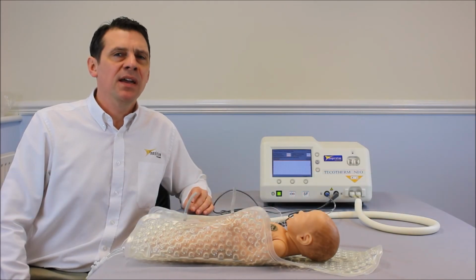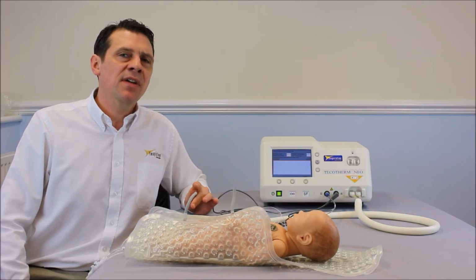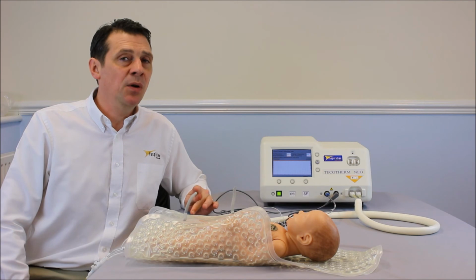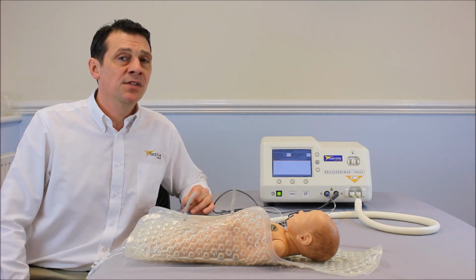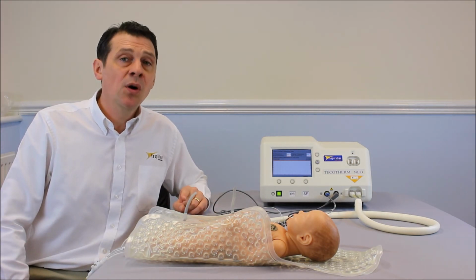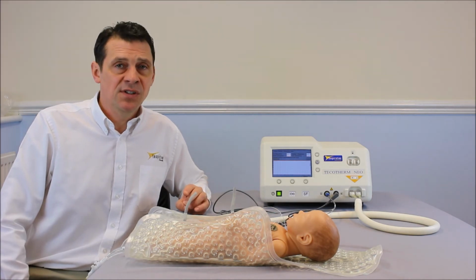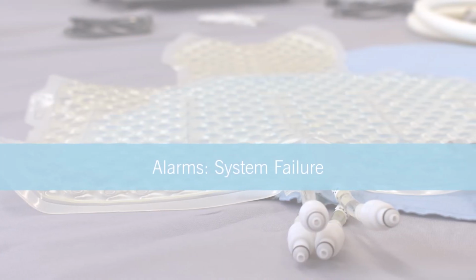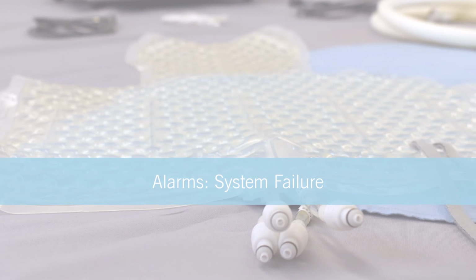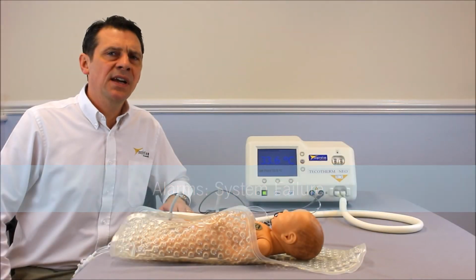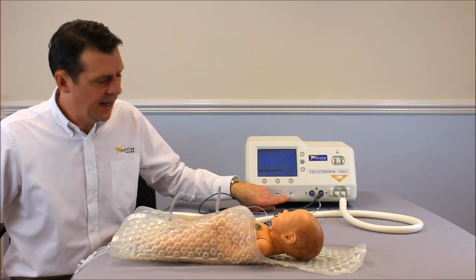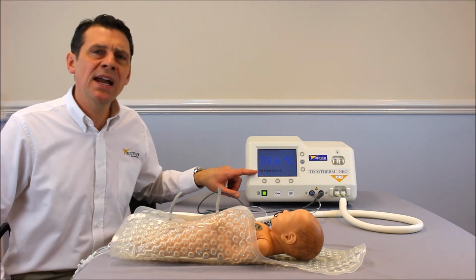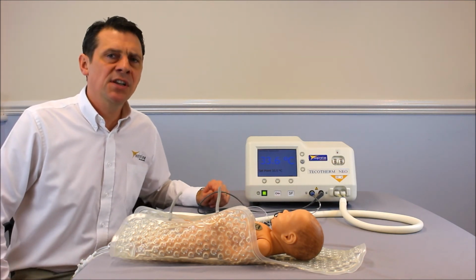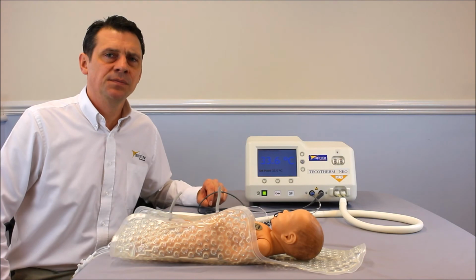A temperature alarm may occur if there is a deviation outside of the range of half a degree either above or below the set target temperature. To correct this, we may check the rectal probe, or again check the fluid level of your mattress. The system failure alarm is SF. That may appear on the bottom right hand side of the screen. That means there is an internal fault within the machine itself.